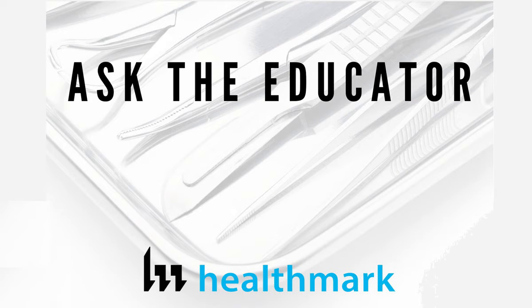Sure. So like I had said earlier, it goes back to the steps of processing not being followed as per IFU and as per their own reference standards, guidelines, or policies. So pre-cleaning, I've seen it where for Olympus scopes, the air water channel cleaning adapter is completely not used. It was left in a cabinet or storage area somewhere. That is a prescribed step of processing that has to be followed, and the only place that can occur is in the procedure room while the scope's still hooked up to the processor.